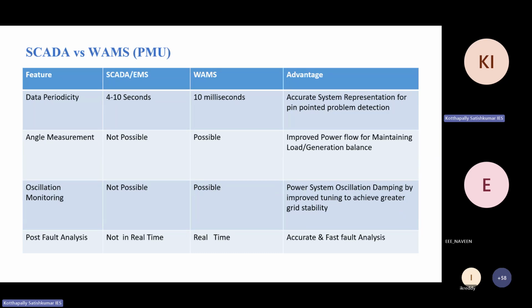In terms of data periodicity, the SCADA system reports every 4 to 10 seconds, whereas the present PMU technology senses data from the power system, from substations to control centers, every 10 milliseconds. So you can see around a 1,000-fold improvement in the speed and accuracy of data from PMUs compared to SCADA. With SCADA, data updates every 4 to 5 seconds, but with PMU or WAMS technology, data is reported to the control center every 10 milliseconds, giving much more accurate data.